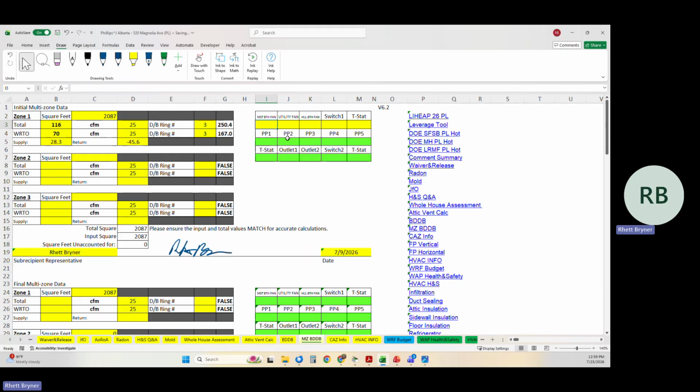All right. So the first one here, master bath fan, is 47 CFM for leakage. Next one is 50 for the utility fan, and then the hall bath fan was 49.5. So quite a bit of leakage from those. Oh, and that's not actually CFM, that's pascals during the test. So that's a different term there.